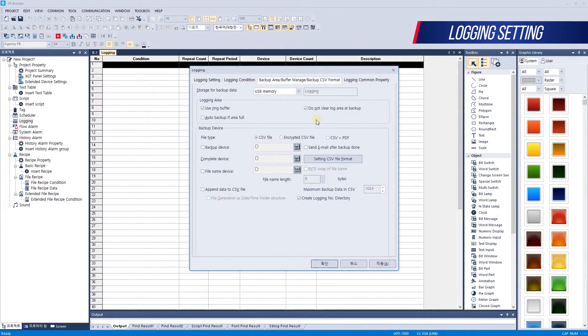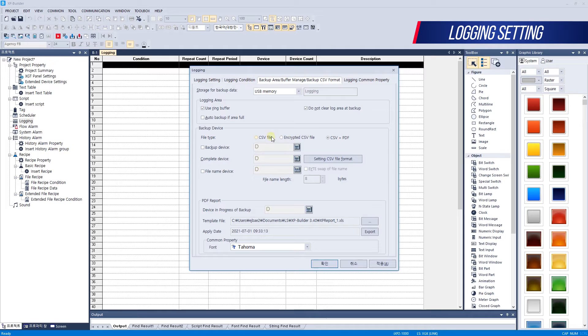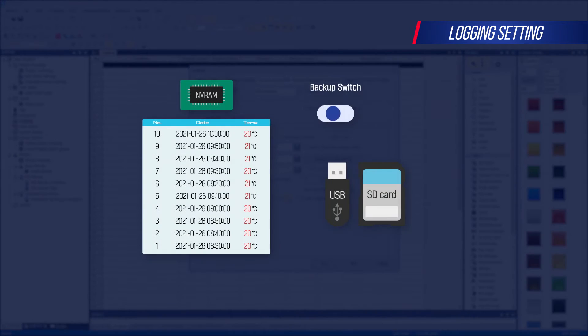When the user uses the logging backup, logging data in NVRAM is moved to the backup storage device and logging data in NVRAM is deleted. However, if you set Do Not Clear Log Area at Backup, logging data will not be deleted even if it is backed up. Backup files are saved as CSV files, encrypted CSV files, or PDF files. To backup, you must set a backup device. When the set bit device is on, it backs up logging data stored in NVRAM to the external storage device. You also need to set up the backup completion device, which turns on when the backup is complete.